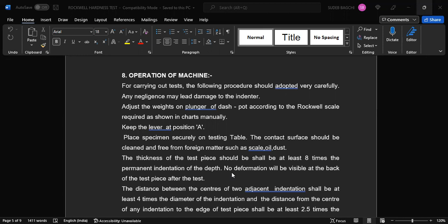And from the edge of the test piece, the indent should be around 2.5 times the diameter of the indentation, unless specified otherwise. So there are 2 positions. From one indent to the next nearby indent, it should be around 4 times the diameter of the impression, and the indent should be at least 2.5 times away from the edge. So we can use our test pieces a number of times, but we have to follow these conditions.